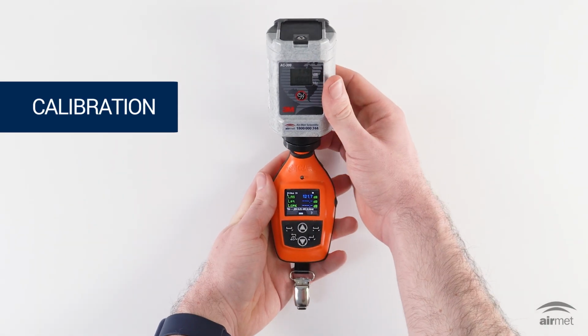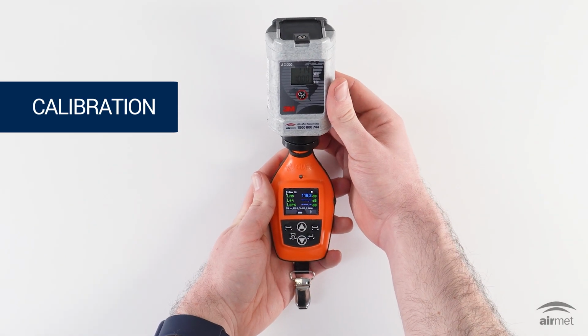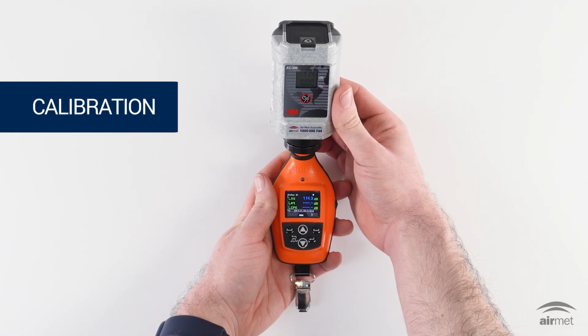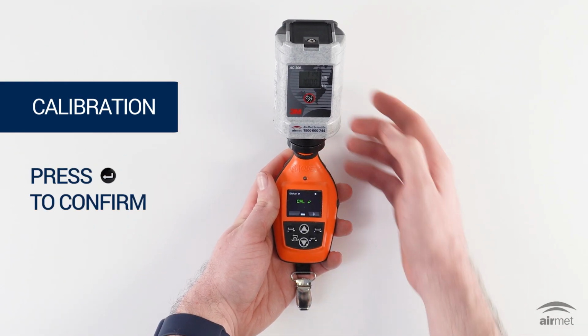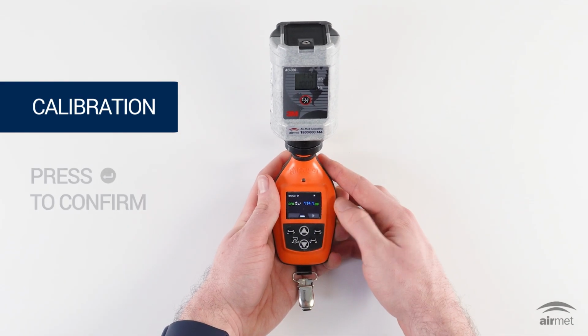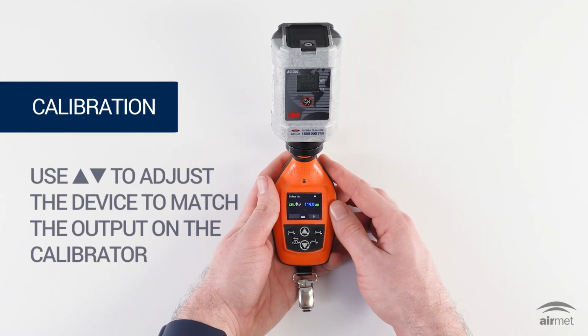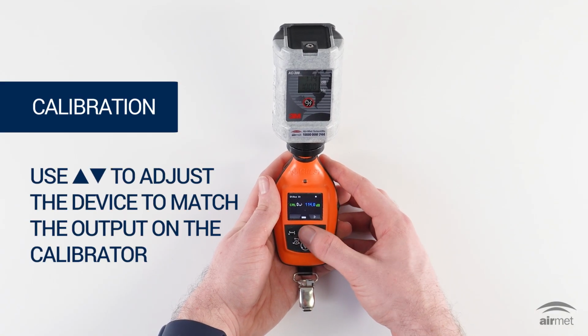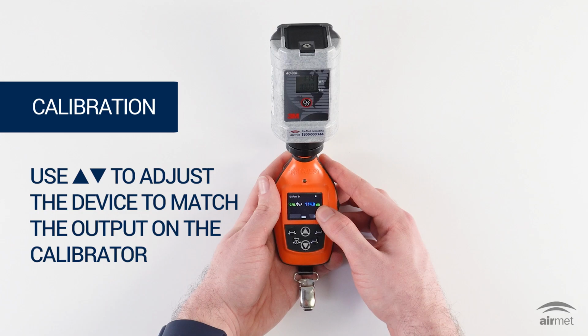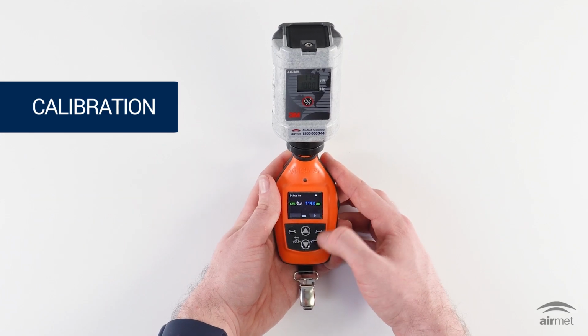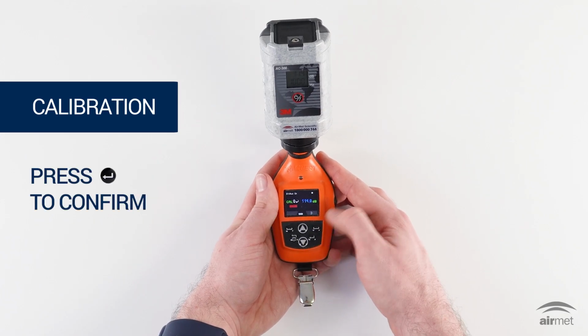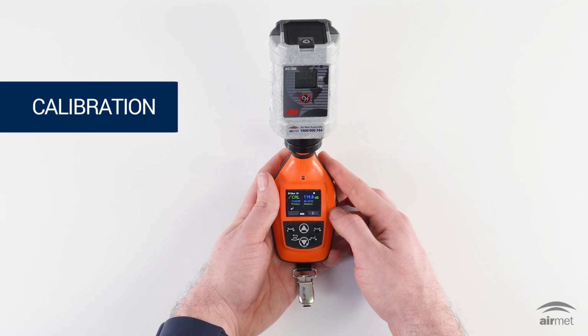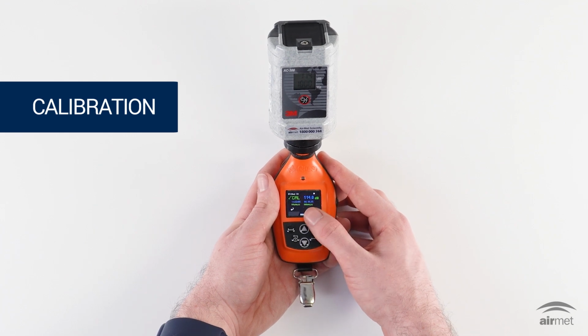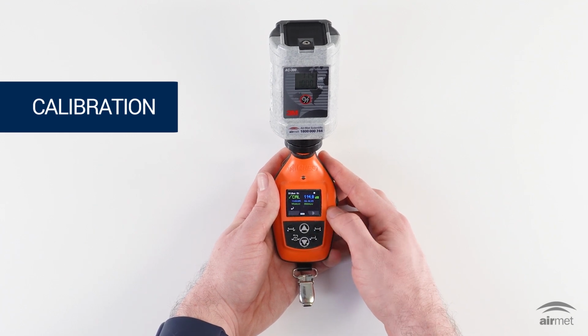After a couple seconds, the unit will enter calibration mode. Press Enter to confirm. Next, adjust your readings using the up and down soft keys until you reach your desired 114 decibels. Press Enter to accept the calibration. The unit will display your calibration results, as well as the time and date the unit was calibrated.